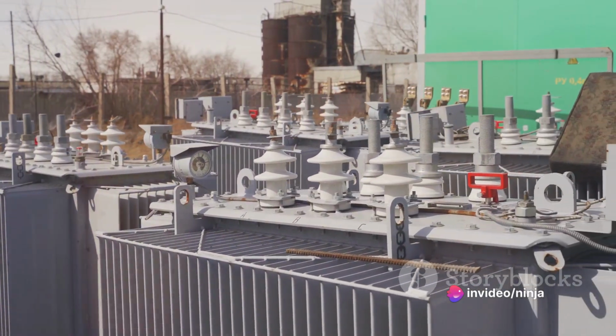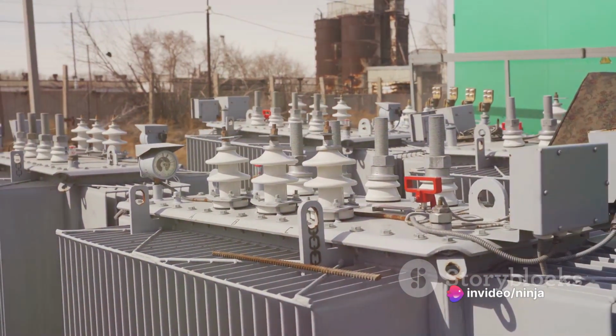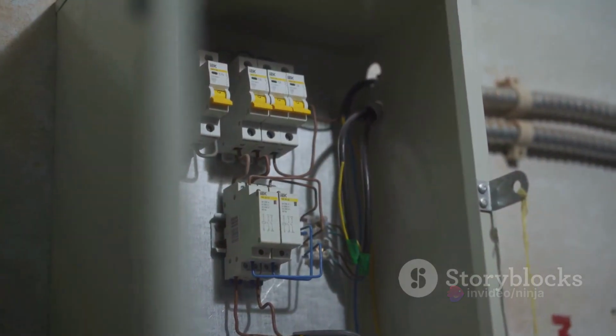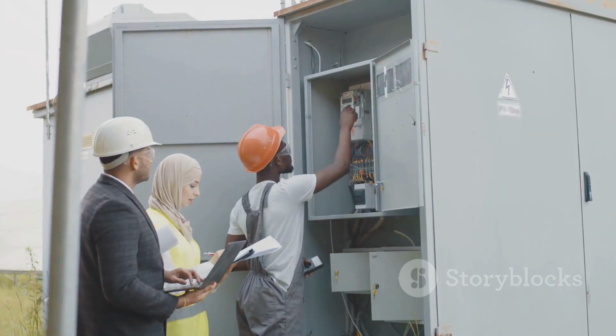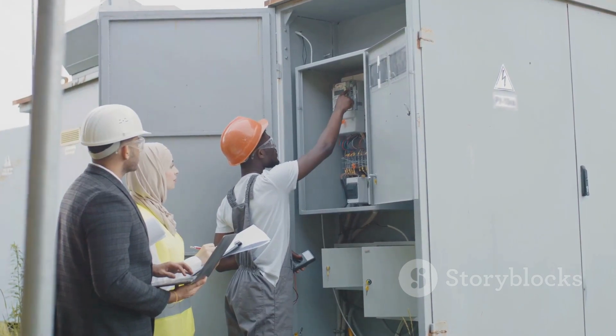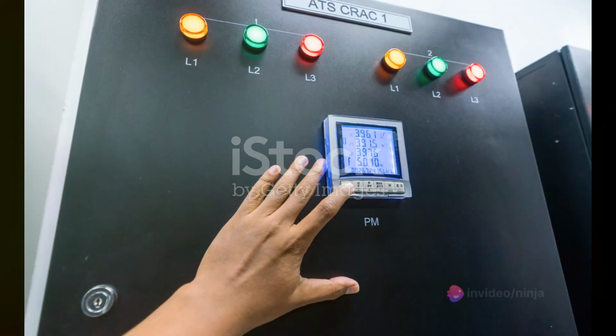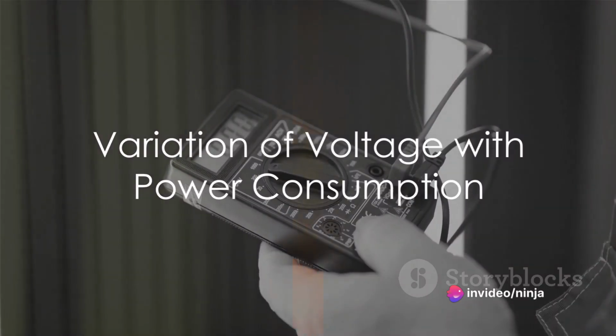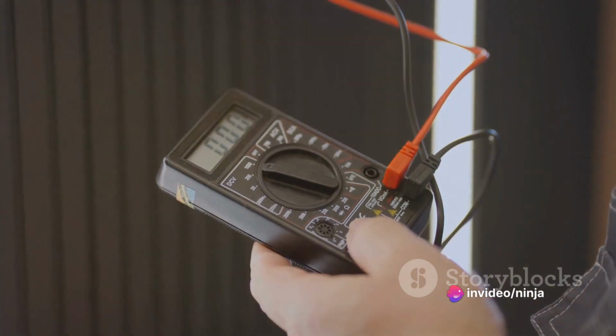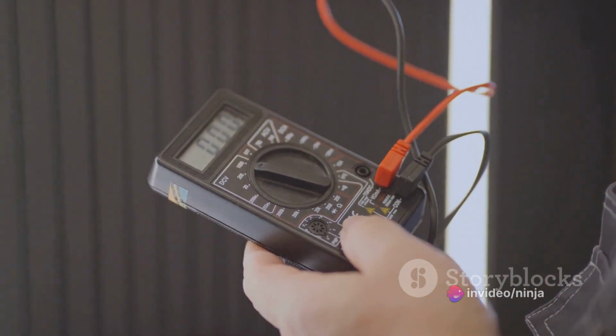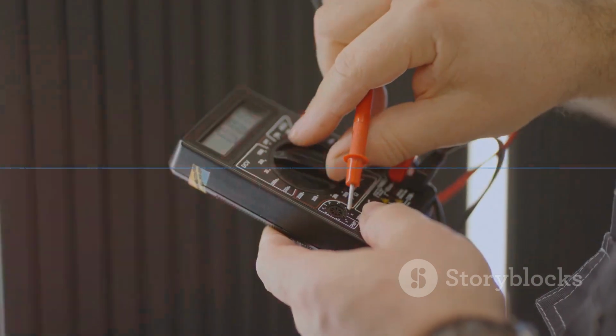Picture a high voltage to medium voltage transformer, for example 70 to 20 kilovolts. The voltage on the secondary side is kept within a certain deadband by means of the automatic tap changer of the transformer. As power consumption increases or decreases, the voltage along the medium voltage feeder varies. It drops when consumption is high and rises when consumption is low.